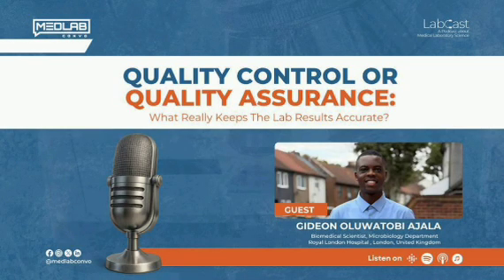Let's go back to the machine. Something must have happened. So we went back to the laboratory. We checked the machine. We did the QC. The QC failed. Wow, this definitely has something to do with the machine. So we had to check the reagents, troubleshoot, and we discovered the error. It was fixed and the sample was done again. From a PCV of around 14, I think it was 14 that day, we got a result showing the guy was actually okay. Everything came out perfectly. The PCV was around 40 something.